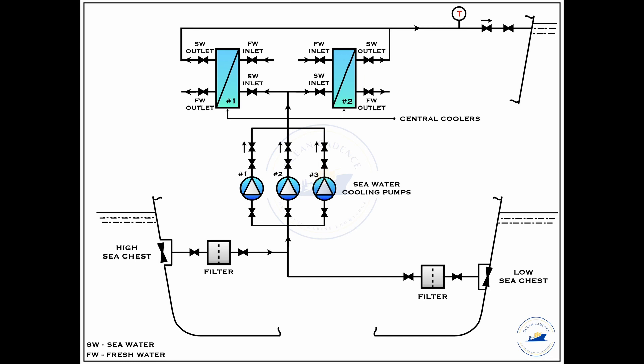As I had discussed before, if we have a backflush arrangement we can use it directly to clean the filter and increase the temperature gradient, so we have a more optimum running condition. Or in case if the backflush arrangement is not present, then we have to use manual cleaning methods by isolating the cooler one by one by closing the inlet and the outlet valves that are present in the circuit.